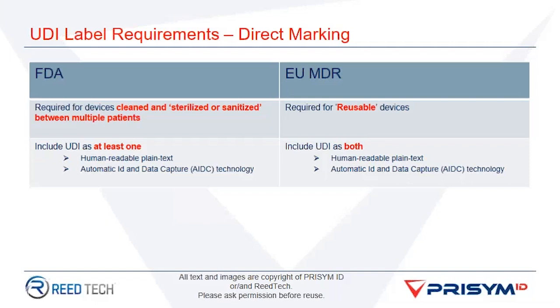If our device isn't to be reprocessed at all, it's single use only, we currently use the 2 with the circle and line through it, I guess as a symbol for single use. Will we need additional indicators? No, I believe the single use symbol would only be applicable in your scenario. A 2 with the line through it crossed out, indicating not using it a second time.